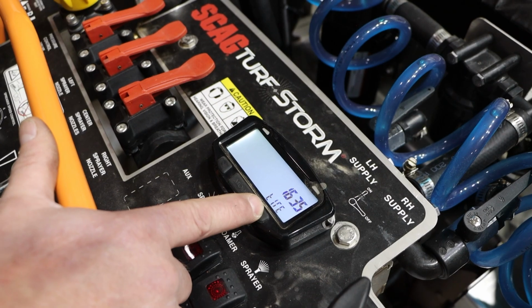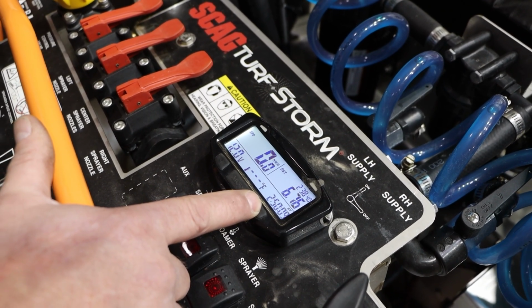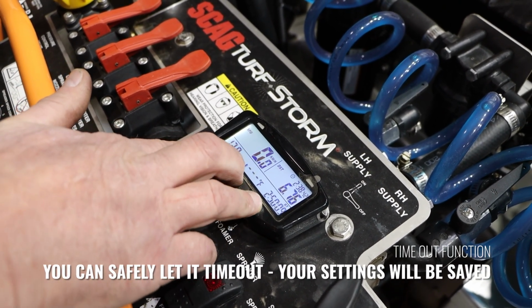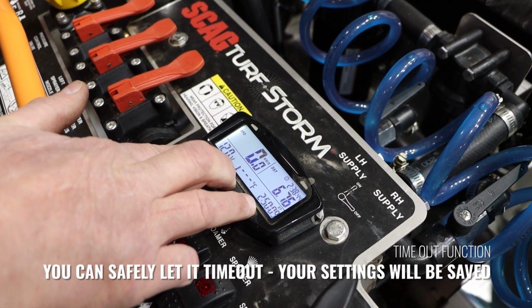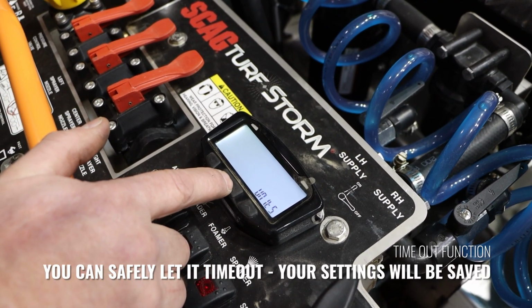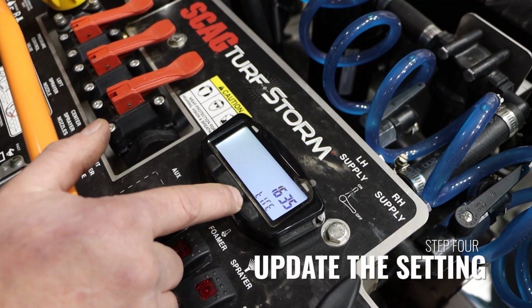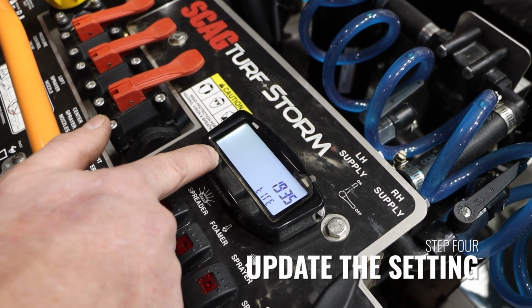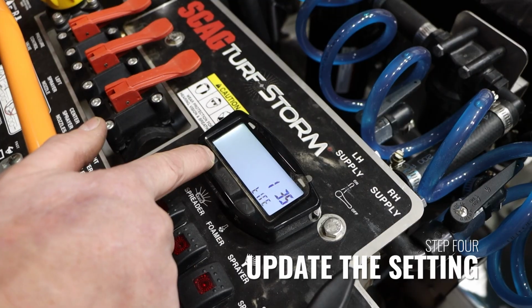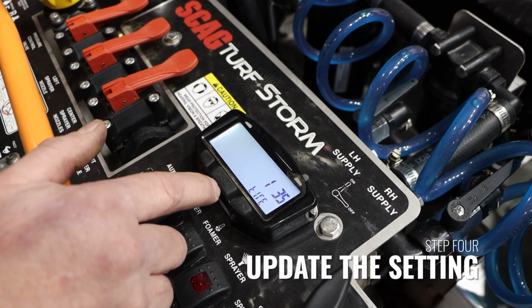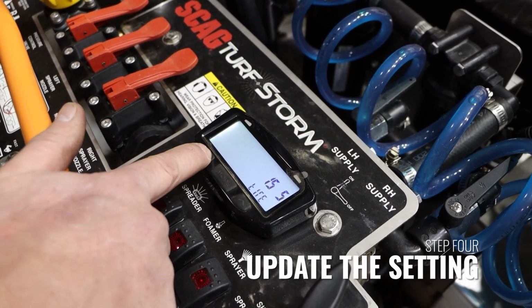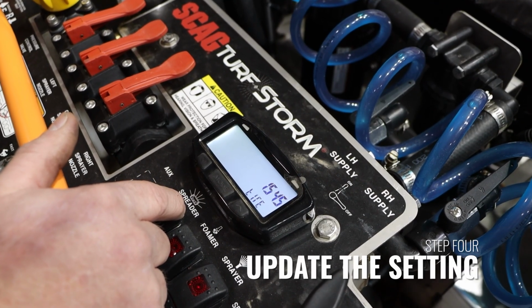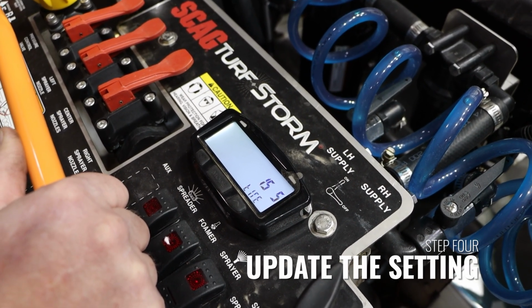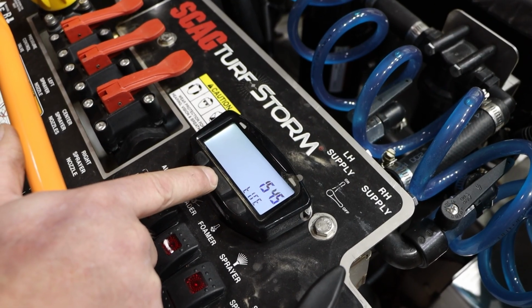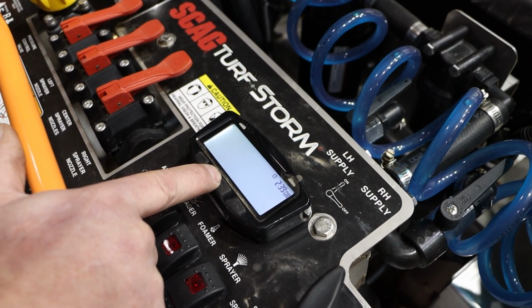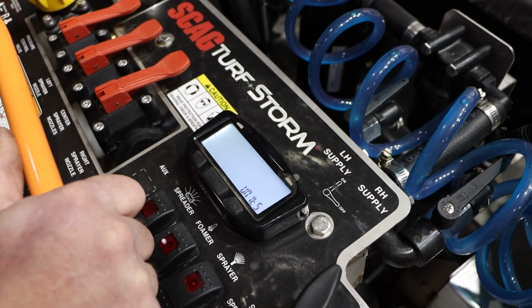Ken, the factory setting was 1635, but we need to change that to our setting of 1545. You'll notice that there is a timeout on the module that we just showed you. So Ken's going to go right back in, and now that he's working, it's going to continue to stay on for us. That is a timeout, just in case you forgot. 1545 is our value, and when he is done, he could hit the mode button to go forward, or he can simply let it time out and go back to the main panel.